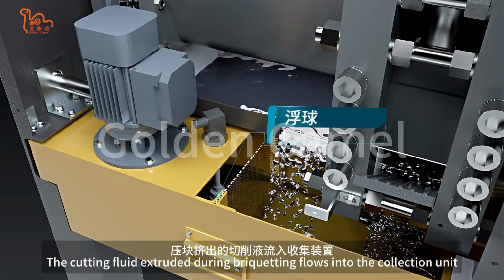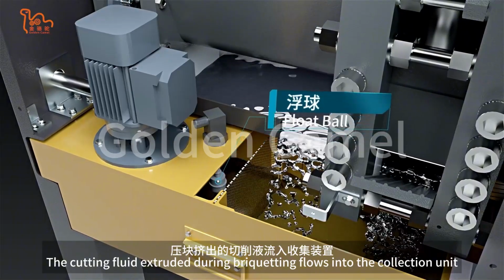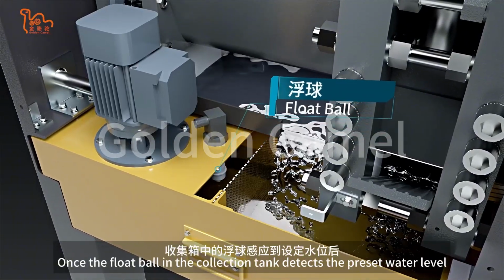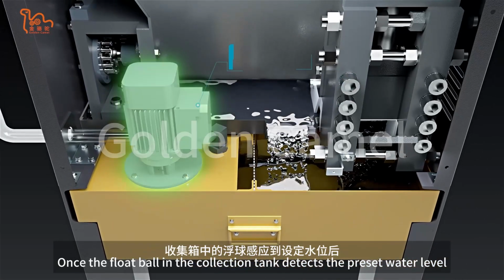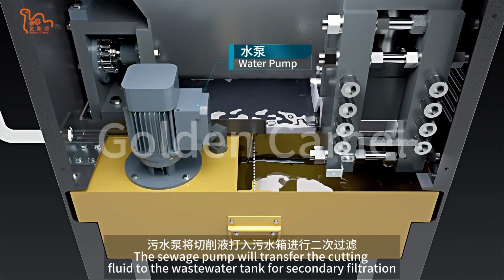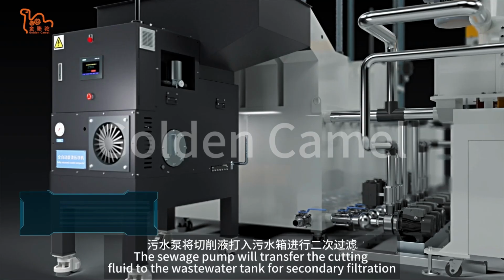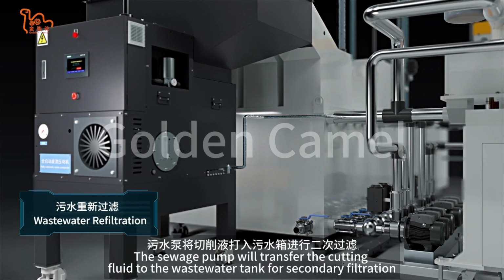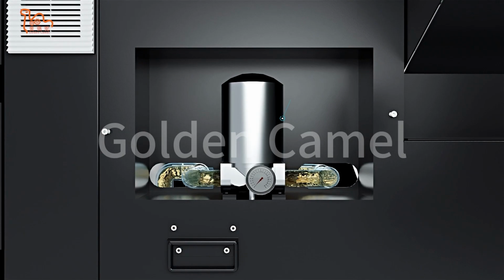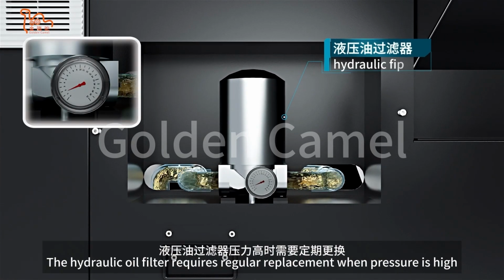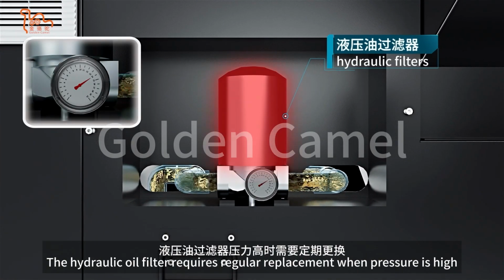The cutting fluid extruded during briquetting flows into the collection unit. Once the float ball in the collection tank detects the preset water level, the sewage pump will transfer the cutting fluid to the wastewater tank for secondary filtration. The hydraulic oil filter requires regular replacement when pressure is high.